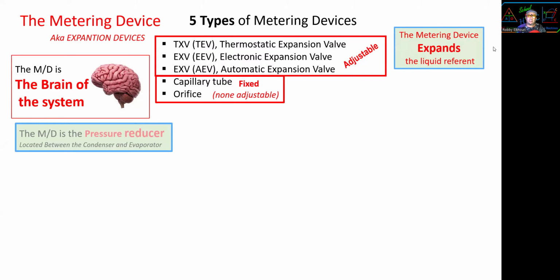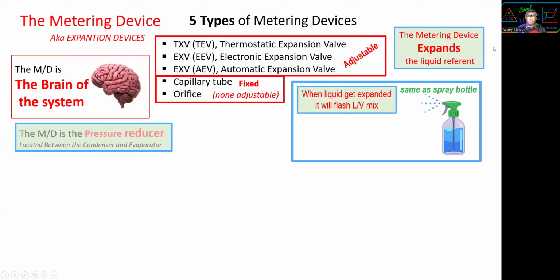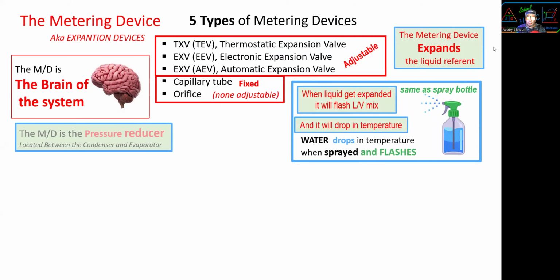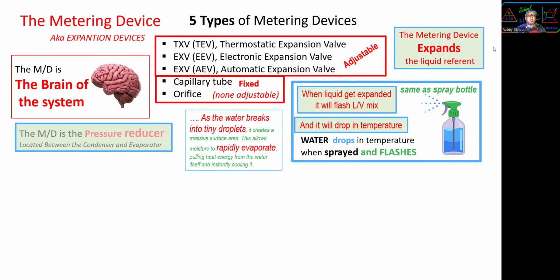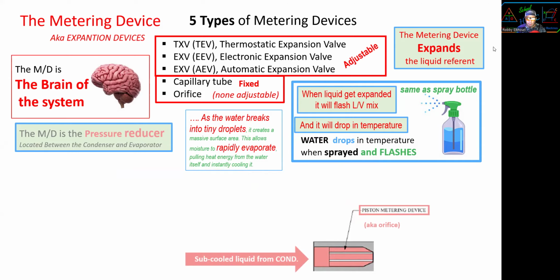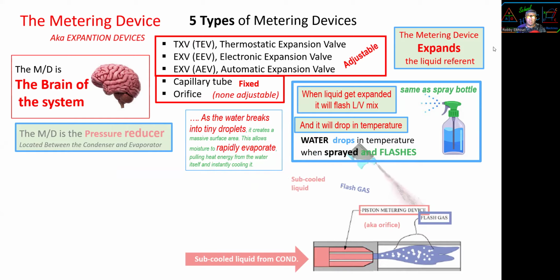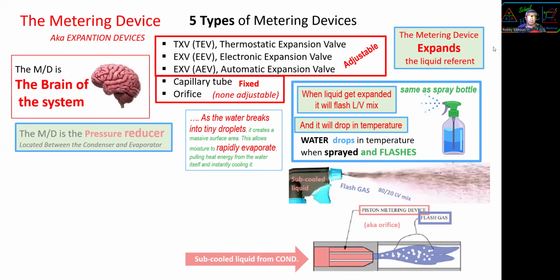The metering device is the pressure reducer located between the condenser and evaporator. The metering device expands the liquid refrigerant, same as a spray bottle. When liquid gets expanded, it will flash to a liquid vapor mix and will drop in temperature. Water drops in temperature when sprayed and flashes, as it goes into tiny droplets, rapidly evaporates and cools down. You can Google the physics. Then we have a piston metering device, which is also the orifice. Sometimes they call it piston, sometimes they call it orifice. Subcooled liquid from the condenser comes in and flash gas comes out, just like a spray bottle, 80-20 mix.